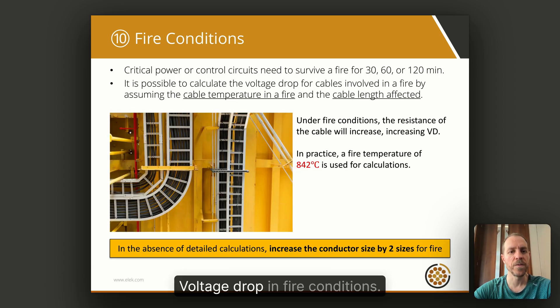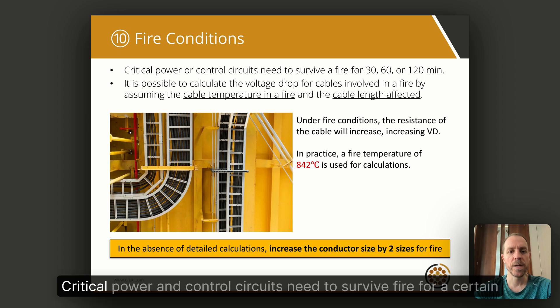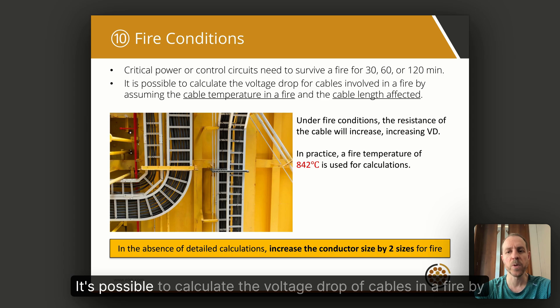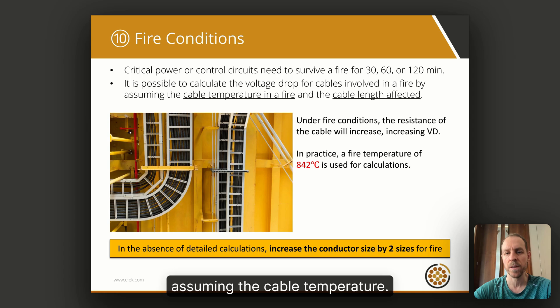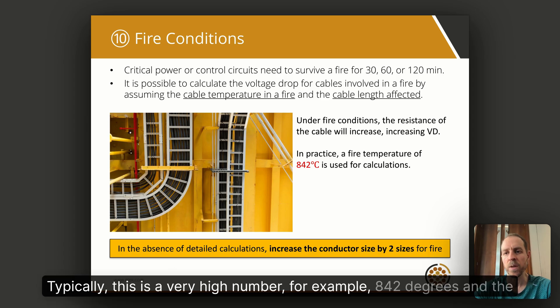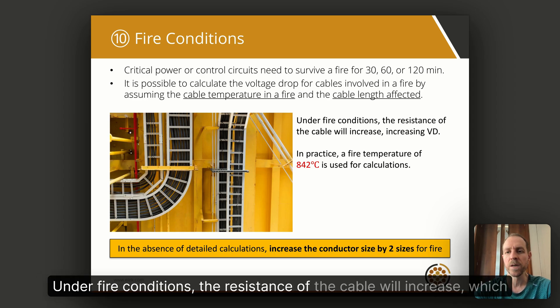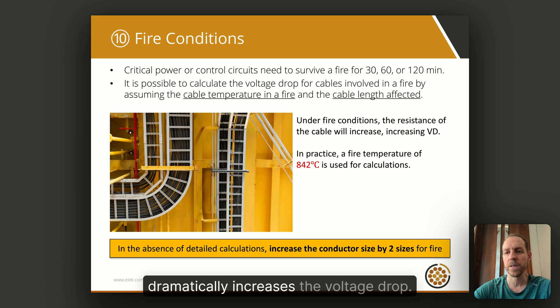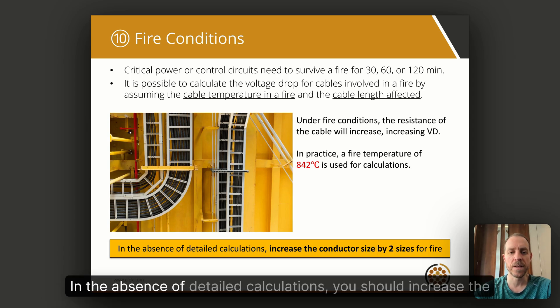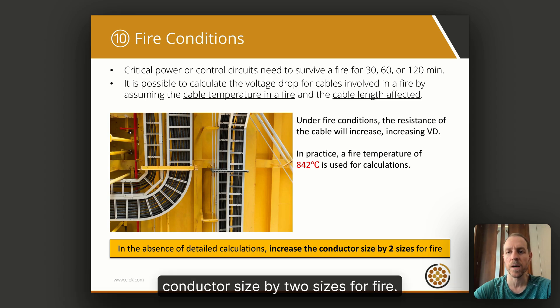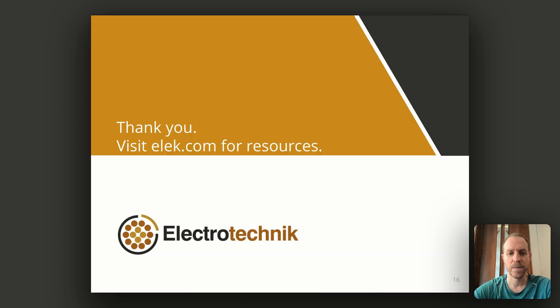Tip number ten: voltage drop in fire conditions. Critical power and control circuits need to survive fire for a certain amount of time. It's possible to calculate the voltage drop of cables in a fire by assuming the cable temperature — typically this is a very high number, for example 842 degrees — and the length of the cable that's affected by the fire. Under fire conditions, the resistance of the cable will increase, which dramatically increases the voltage drop. In the absence of detailed calculations, you should increase the conductor size by two sizes for fire.